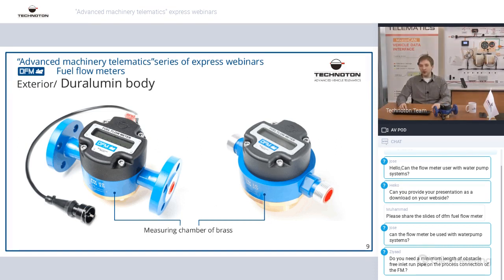When you're in talks with our sales team, first of all, flow rate is quite important. Secondly, we also need to understand what connector should be used, either thread or flange. If you order a flow meter with a flange but in reality require one with a thread, you'll need an additional connector, additional work, and additional expenses. So please note the type of connector used on the fuel lines when reviewing the application, whether it's a truck, diesel generator, or any other application. Try to get the flow rate, minimum and maximum, first - that would be ideal for us. Secondly, the type of connector, either thread or flange.